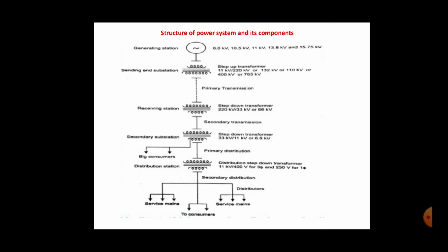Once electrical power reaches the secondary substation, the distribution of electrical power starts. First, the electrical power is stepped down from 33 kV to 11 kV or 6.6 kV. Very large industrial consumers may be served from the secondary substations. Then it can be safely distributed through the primary distribution line.